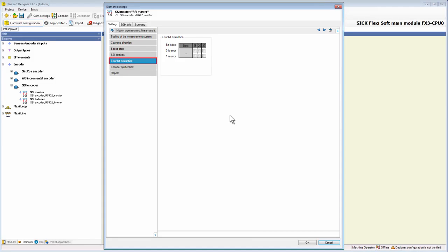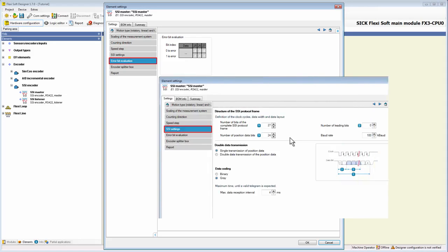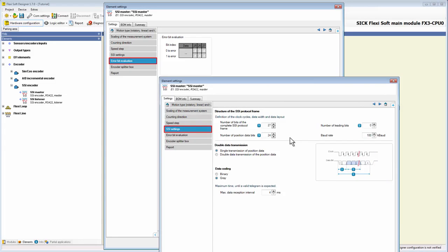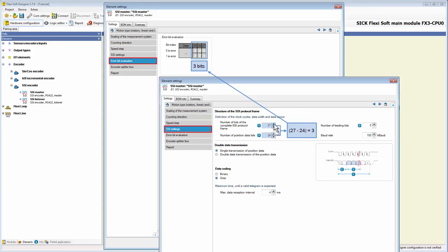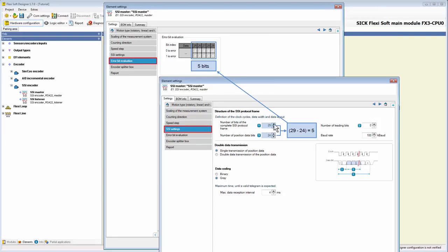These error bits can be generated by the parameters of the previously discussed tab SSI settings. Each bit which is not position data bit can be used as an error bit. So you can either use the unused bits of your SSI protocol frame as error bits, which are generated by the difference of the parameters, number of bits of the complete SSI protocol frame and the parameter number of position data bits.